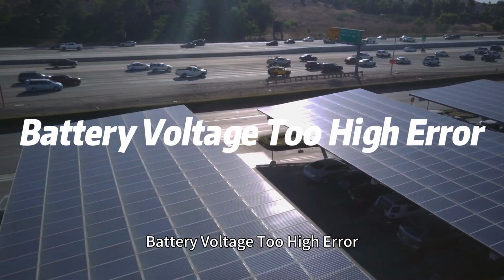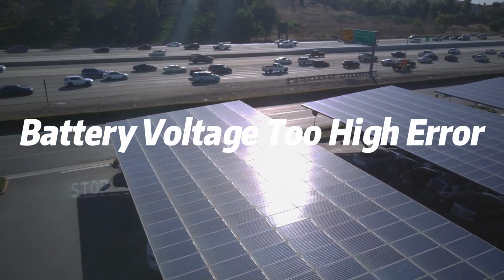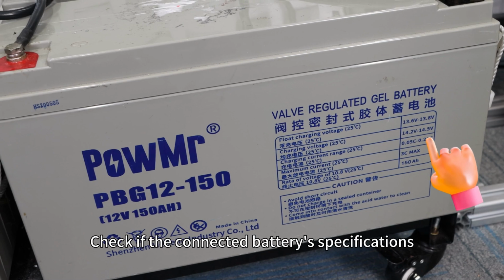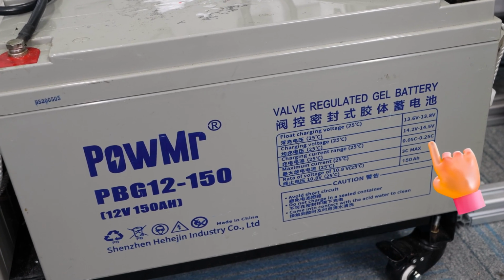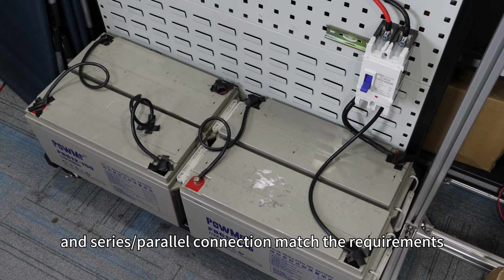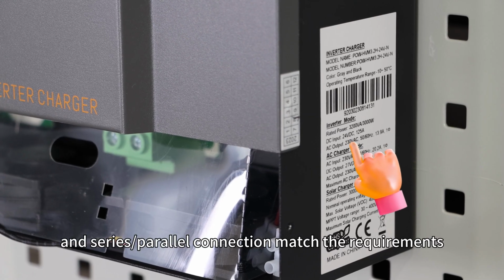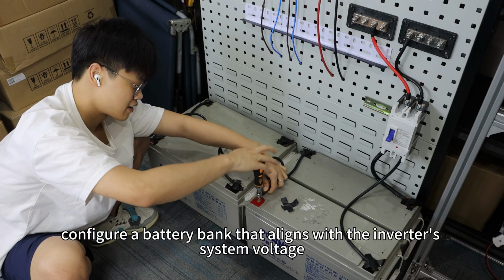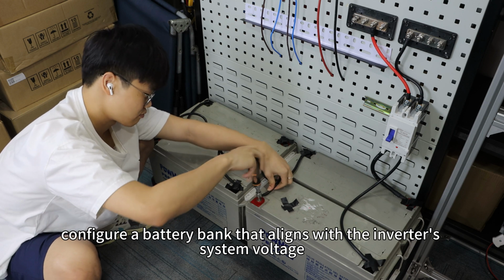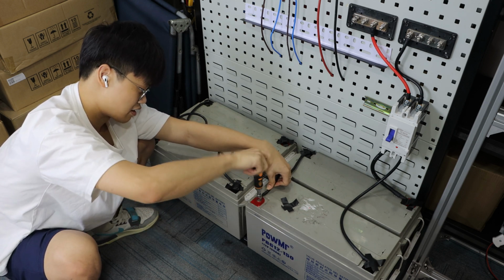Battery voltage too high error. Check if the connected battery specification, quantity, and series or parallel connection match the requirements. To solve this, configure a battery bank that aligns with the inverter system voltage.